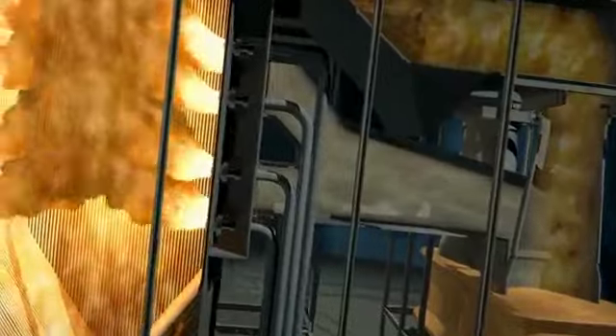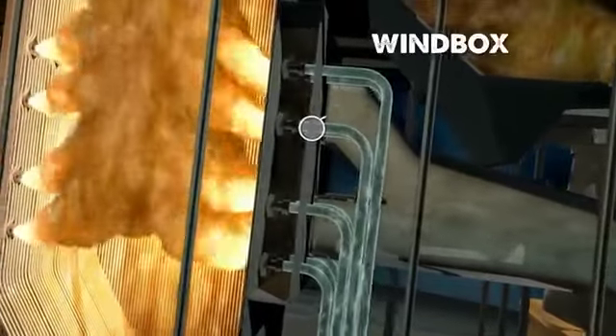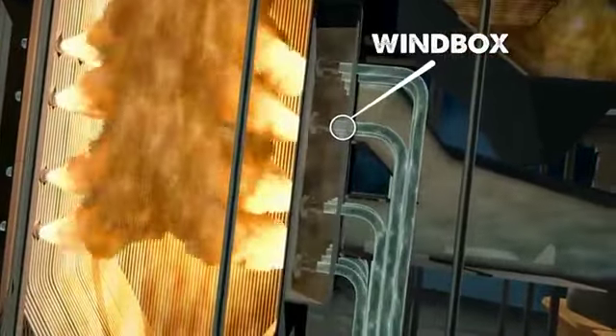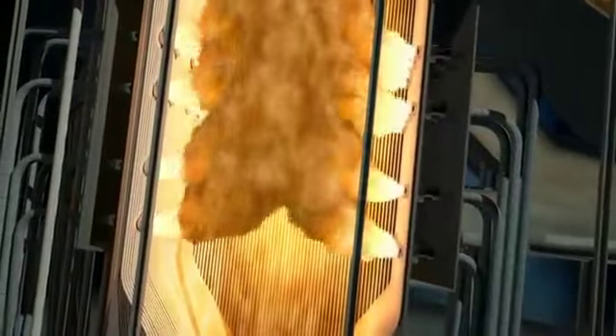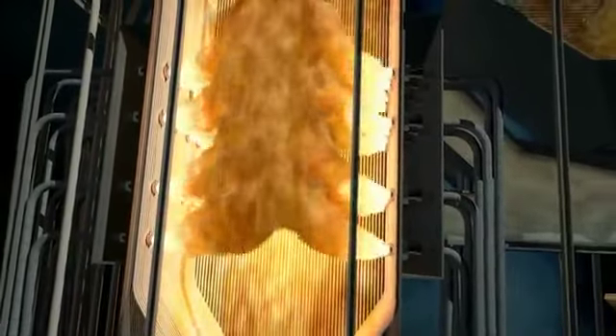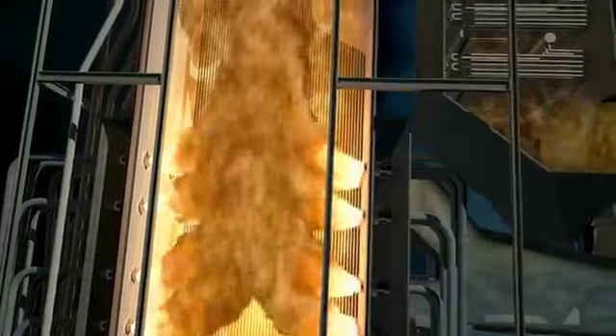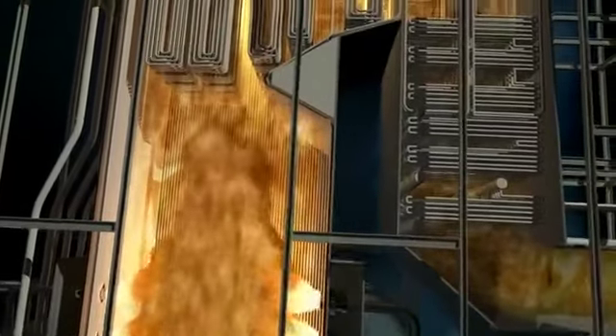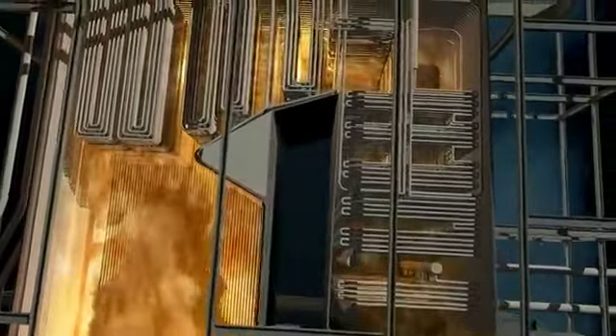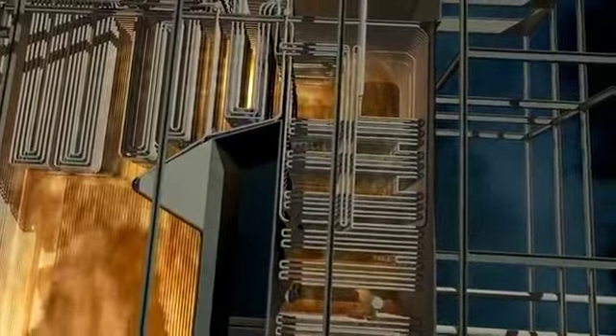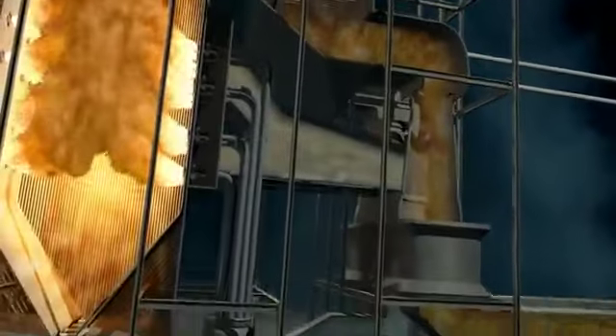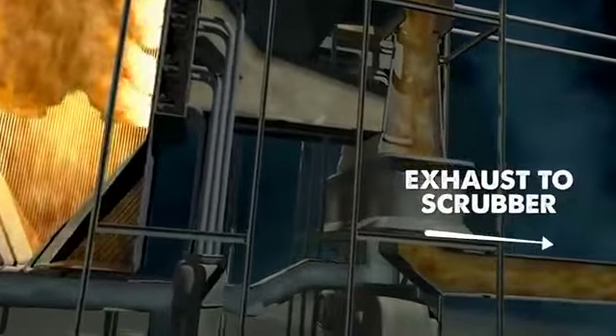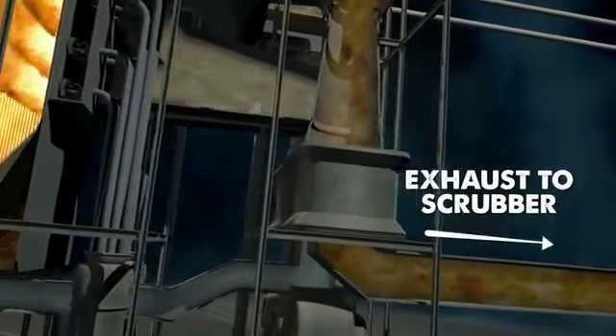The hot forced air and coal dust converge in the wind box, where the mixture is blown out through burners and ignited inside the firebox, transferring radiant heat to the water-filled tubes. The hot gases flow upward, heating the rest of the system through convection, before passing through the air preheater and ultimately flow into the scrubber, where pollutants are removed.